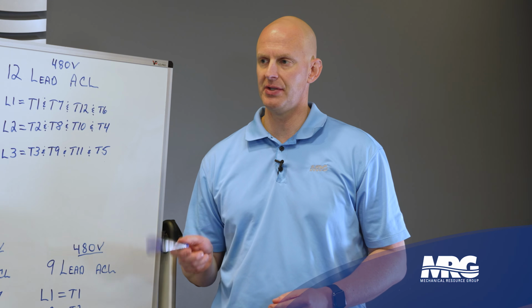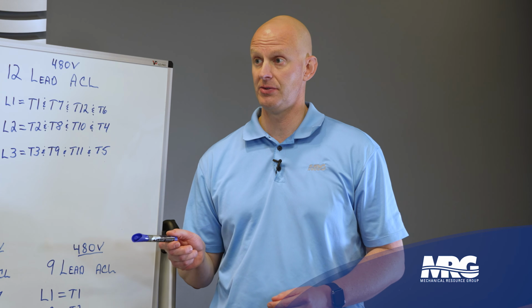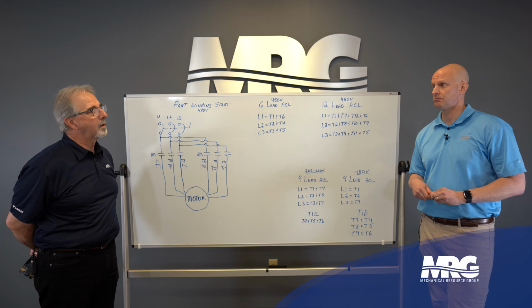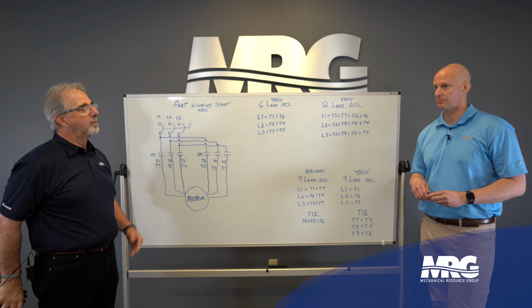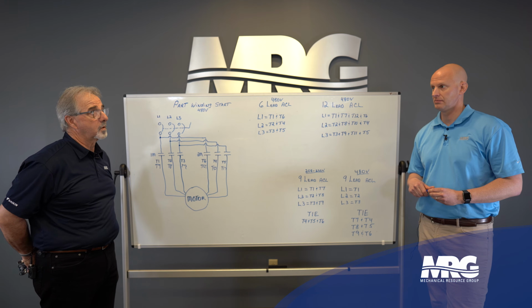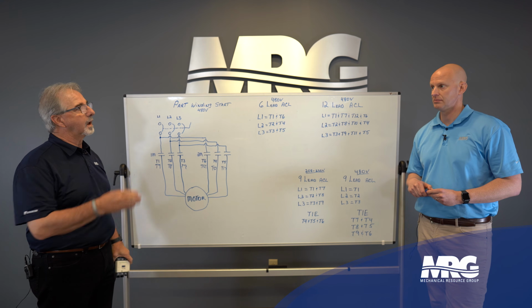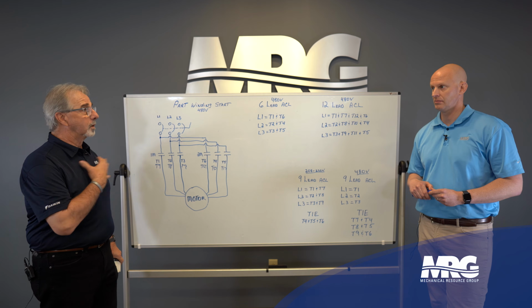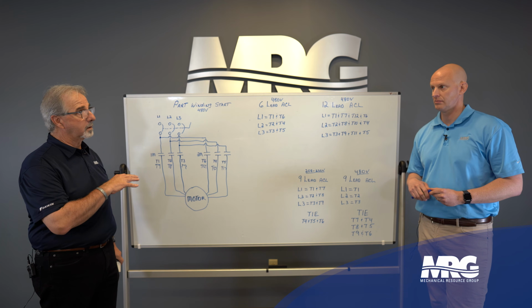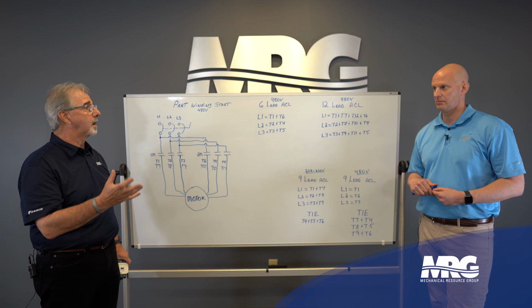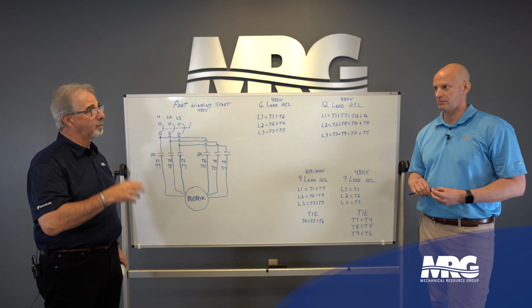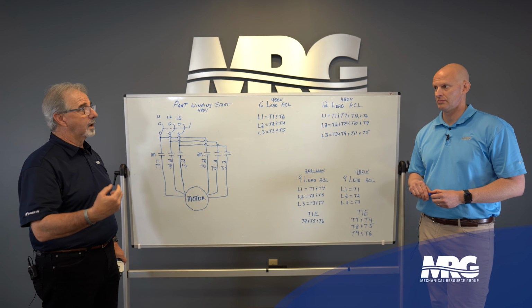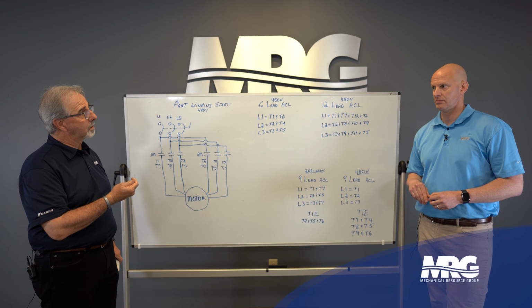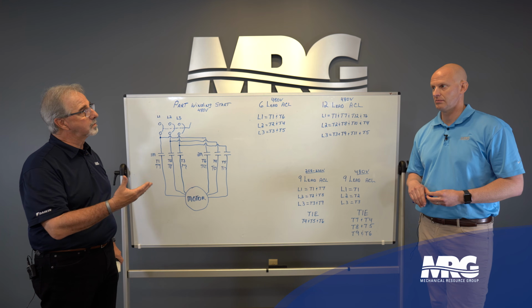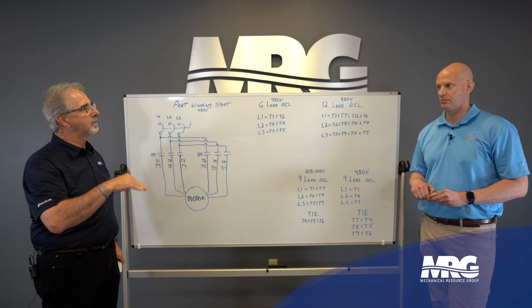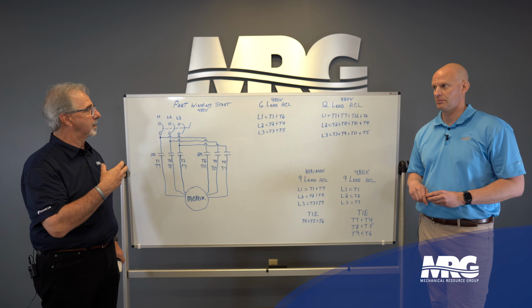Just what would you say the percentage of motor failures, 70, due to wire nuts? Yeah, due to wire nuts. Because wire nuts create loose connections, and remember, motors fail in patterns, just like anything else. And you can tell immediately how a motor failed. So when I worked in the motor shop, I used to do the postmortems and try to determine cause of failure. I had to do root cause. Well, the minute I'd open it up, if 2/3 of the winding was burned up and 1/3 is pristine, first thing I do is go look at the pecker head and see how they connected the motor, because that's a single phase condition. So that's usually what will happen: you'll get uneven current that'll draw through the motor and cause the motor to burn in that type of pattern.